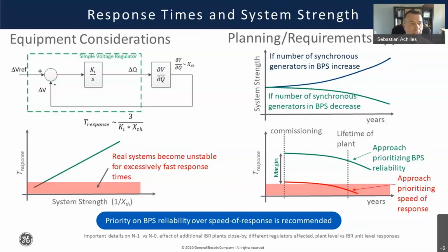If we make that response too fast in real systems, it becomes unstable, because every system has latencies related to communication—delays not represented in this simple diagram. So if the response time gets too fast, it goes unstable, and that tends to happen for a voltage regulator when the system gets weaker. From the equipment standpoint, the response depends on the settings but also on system strength; as system strength gets lower, the regulator's response time gets really fast, and if it gets fast enough, it becomes unstable.